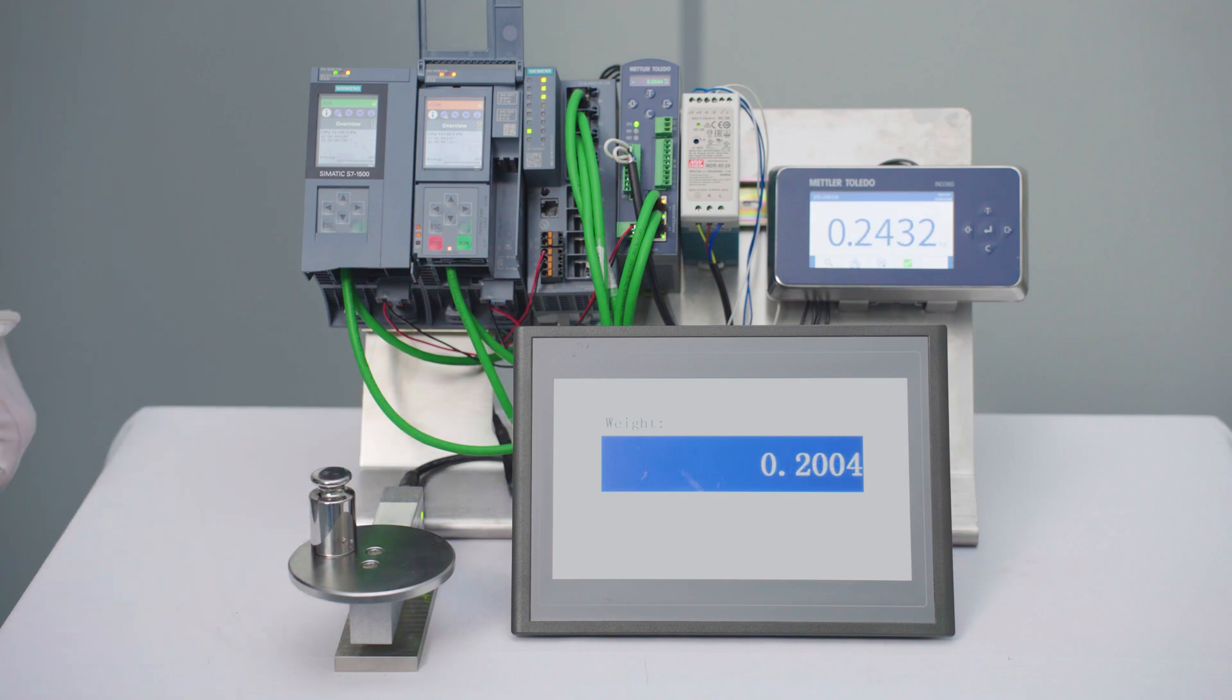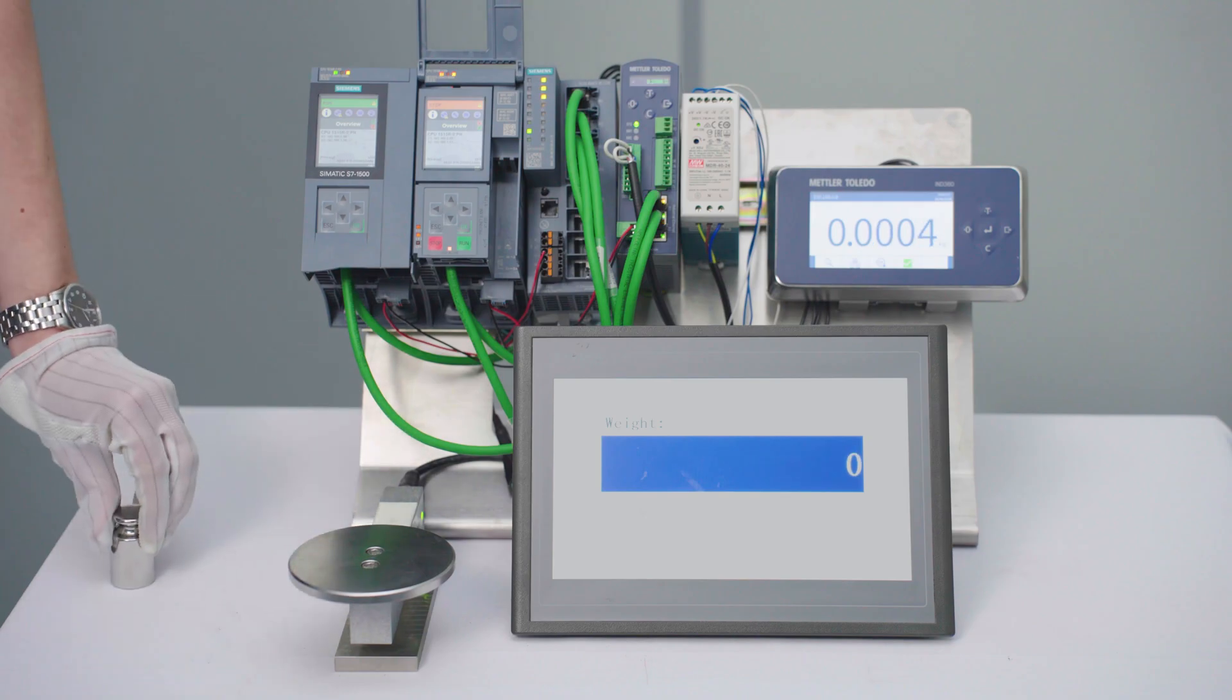I can apply 200 grams of weight and we see 200 grams again, also on the display. And again putting that one to run and it will synchronize back.